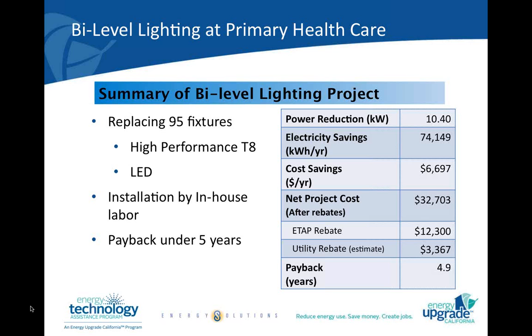So on the right you see the table there, and this is a summary of the project with the power reduction, a little over 10 kW, energy savings, about 74,000 kWh per year, cost savings, about $6,700 per year, with a net cost of about $33,000 with a payback of 4.9 years. This translates to us to a cost savings of about 7 cents a square foot for the parking structure, and then a project cost of about 33 cents a square foot. On this project and all the other projects, where we're at right now is we're just putting together the specs and the drawings. So as to what we'll realize on these, it's going to be till the end of the year before we finish up.